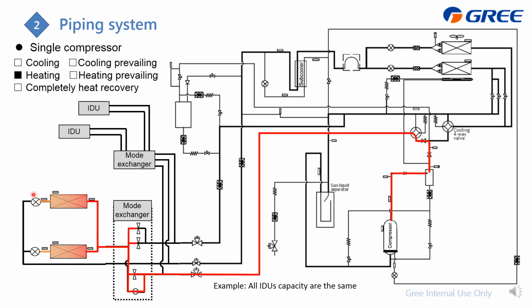And also please pay attention that this EXV will not make the refrigerant get expanded. It just controls the flow rate, which makes the refrigerant balanced, divided into the indoor units. And the refrigerant still remains high pressure, and then we just send the high pressure liquid to the mode exchanger. As there is no valve control here, we will send this liquid directly to the outdoor unit, which just follows this one, and then to this part.